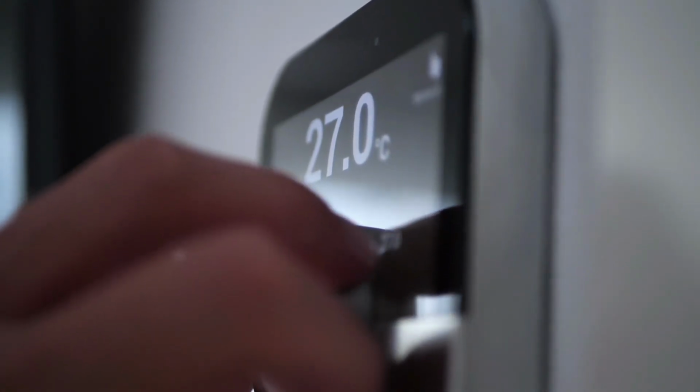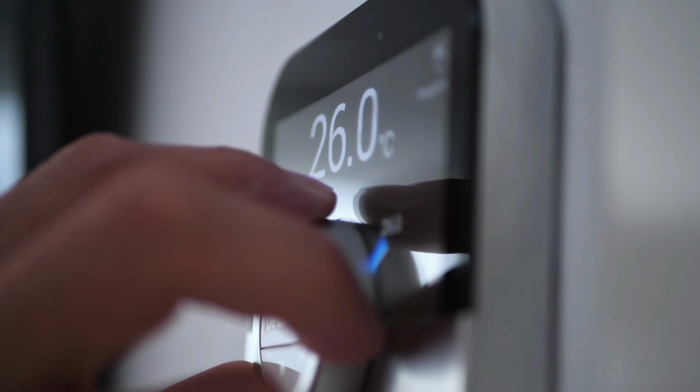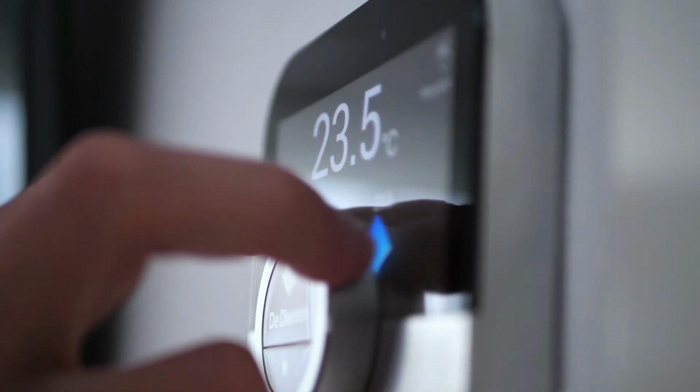We're going to set the air conditioning set point down below room temperature at least 4 or 5 degrees. And the reason why we're doing this is because the first two measurements we're taking are highly dependent on proper airflow, and we want to make sure our system is running at full capacity when we do this. If you have a multi-stage system, 2-stage cooling, if you have variable speed blower motors and things of that nature, dropping that temperature 4 or 5 down below room temperature will ensure your system's running at full capacity so that we get precise measurements to work with.